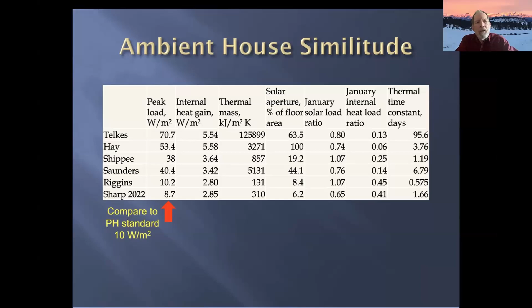The internal heat gains were, for the older houses, something that you could perhaps neglect because they were pretty small. But now, if you're talking about 2 to 3 watts per square meter and the envelope losses are 10, then that's something that you really can't neglect. So much different for the modern houses. Light to heavy conventional construction is like 100 to 400 kilojoules per square meter per degree Kelvin. And you can see that the two modern houses are within that range, but the older houses are well above that. Solar aperture as a percent of floor area is now less than 10% for the modern houses, but it was up to 100% for the older houses.